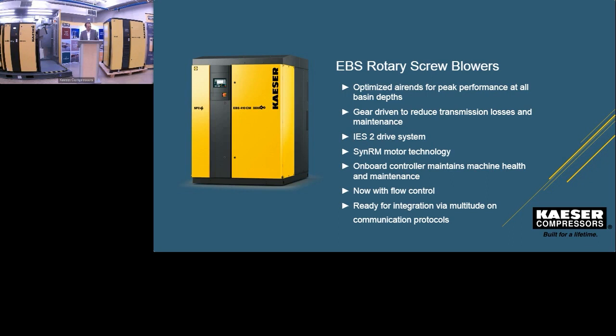The difference between this and some of the newer motors that we see out there are permanent magnet motors. The permanent magnet motor, of course, is efficient and has a lot of benefits from a performance standpoint and size. The synchronous reluctance motor gives us similar performance, but it does not require the rare earth metals. It is manufactured very much in the same way as your traditional motor. So those are some benefits there from a resource standpoint, and it gives us the performance advantage because it is also a no-slip motor.